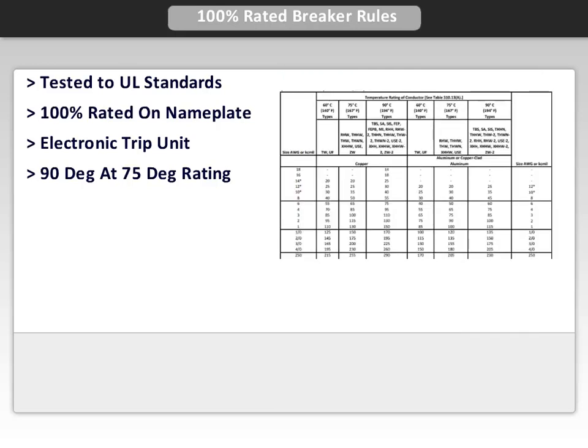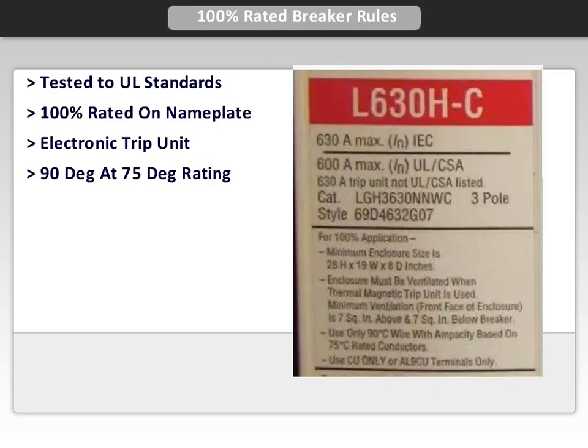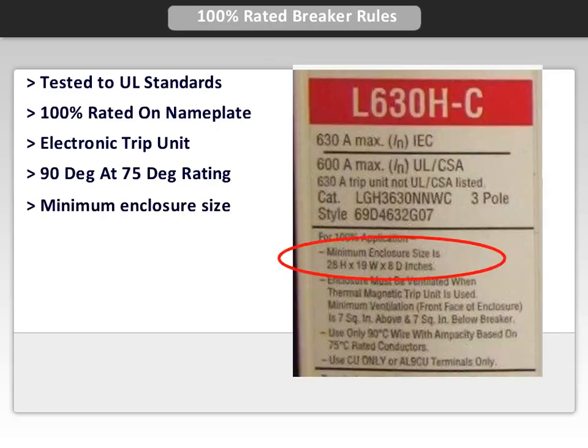Let's look at NEC Table 310.16 for a closer look. Since manufacturers specify that copper wire would be used, we'll focus our attention on that portion of the table. The rule designates that 90 degree cable types will be used, but the current is selected from the 75 degree ratings column. Lastly, UL requires the breaker to be tested with a minimum size enclosure, and that size must be visible on the nameplate.